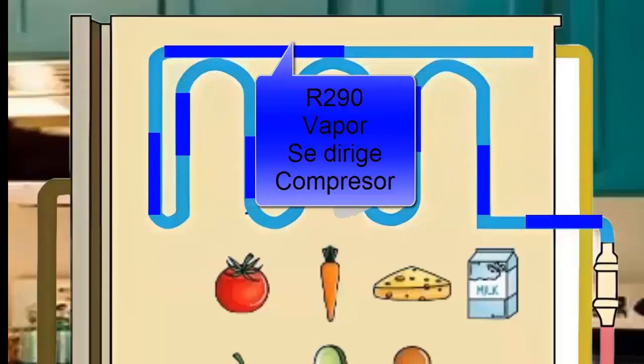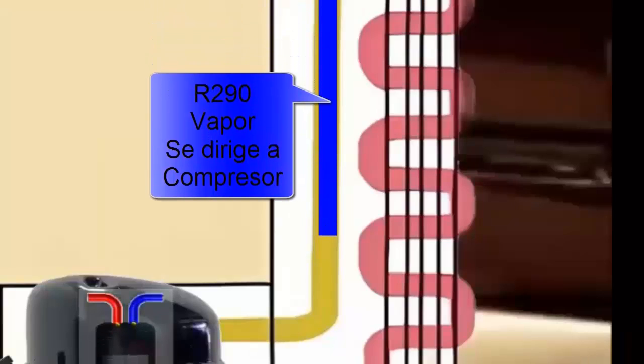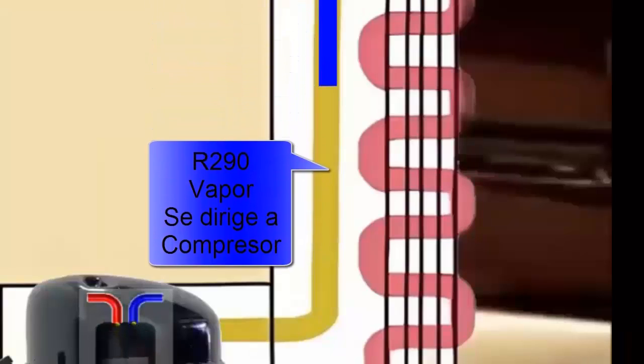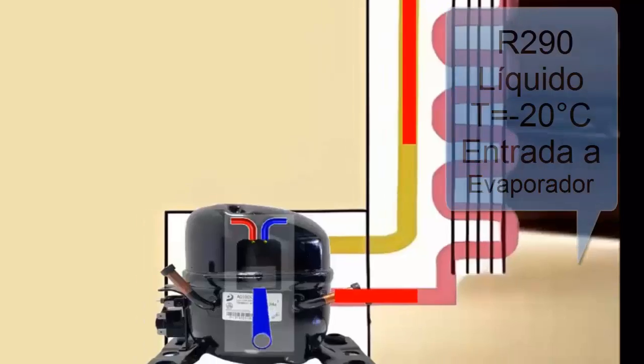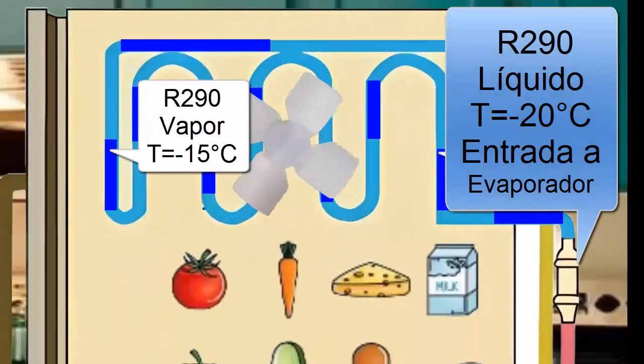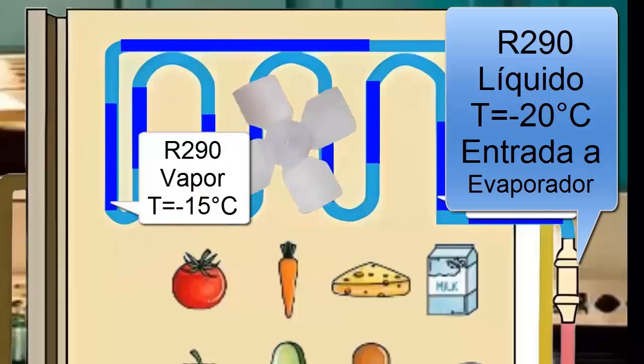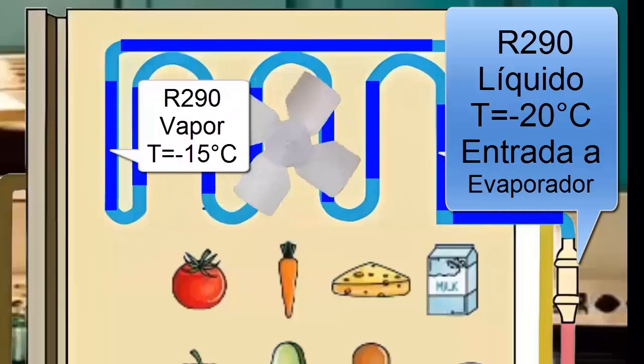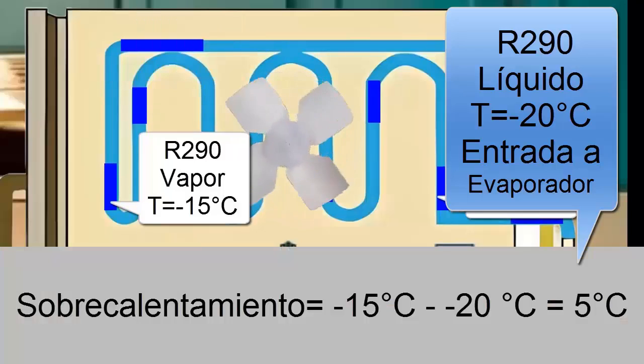For this case, let's assume that the temperature of the R290 refrigerant in a gaseous state, at the evaporator's exit, is minus 15 degrees Celsius. This means that the R290 refrigerant changes from minus 20 degrees Celsius to minus 15 degrees Celsius, resulting in a superheating of 5 degrees Celsius in this equipment.